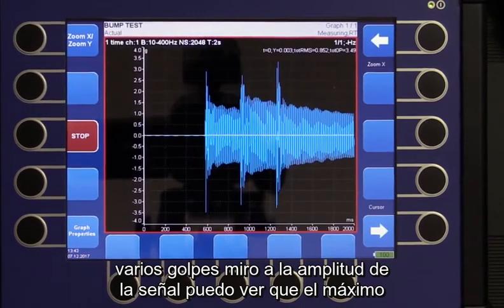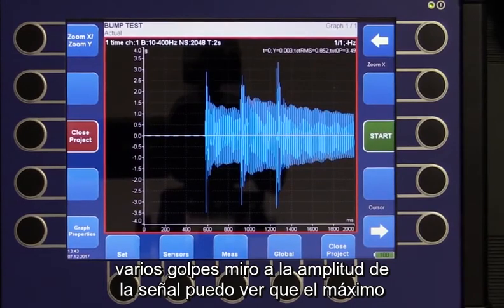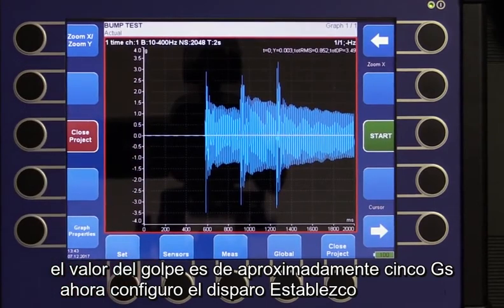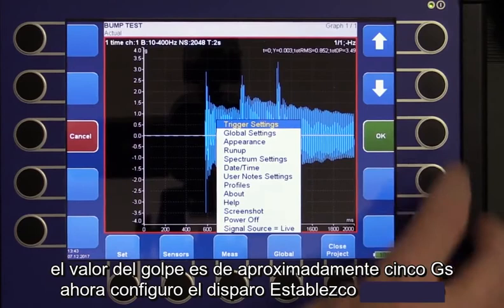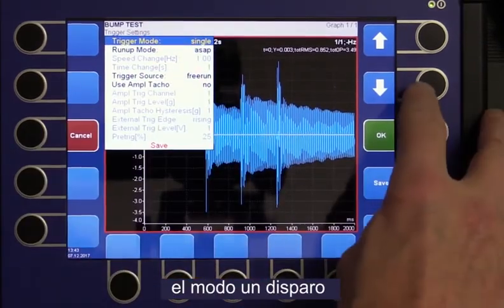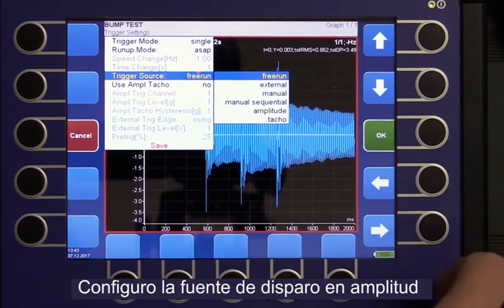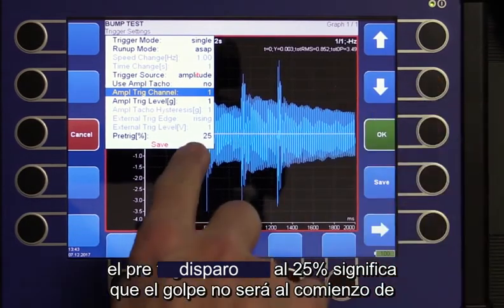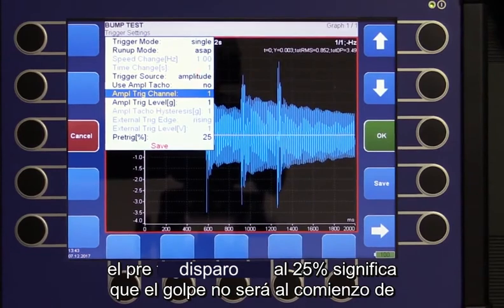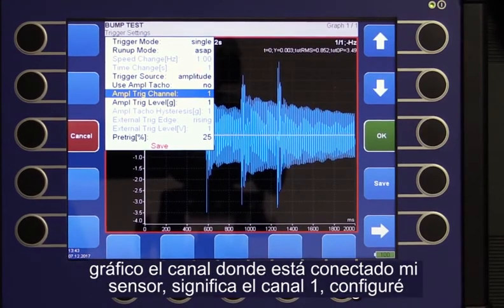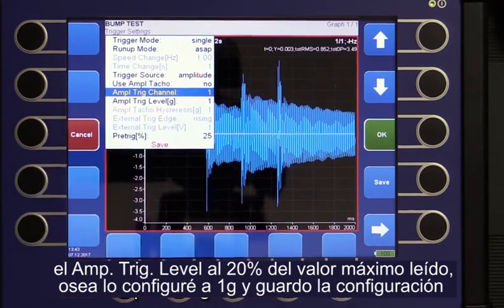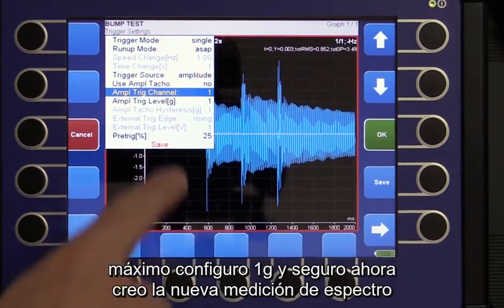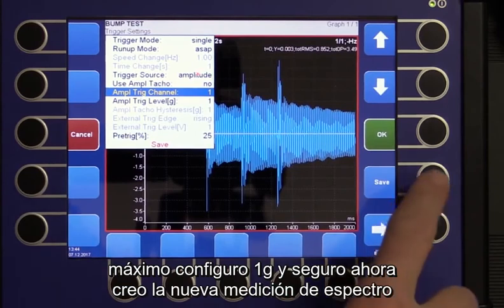I look at the signal amplitude. I can see that the maximum value of the hit is roughly 5 G's. Now I set the triggering: I set single trigger mode, the trigger source to Amplitude, and the pre-trigger to 25 percent — this means the hit will not appear at the very beginning of the graph. The amplitude trigger channel is set to my channel with the sensor, which is the first channel. I set the amplitude trigger level to 20 percent of the reached maximum — 1 G — and save.